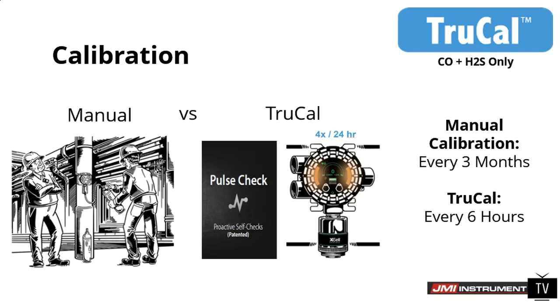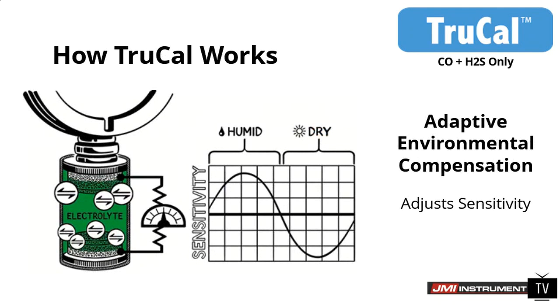And that's basically a self-checking function versus manual calibration that you would typically do maybe once a quarter, maybe once a month, depending on what type of sensor you have or what time of the year it is. Now we're checking the sensor every 6 hours for life and health and adjusting for the sensitivity. When we talk about adjusting for sensitivity, we're talking about the electrolyte loss in the sensor itself, or humidity or temperature changes that could cause the sensor to drift. So we talk about the adaptive environmental compensation. That's a chip that we put inside of these CO and H2S sensors that actually does this pulse check that performs what we call TruCal.